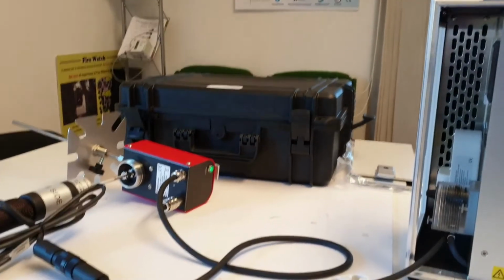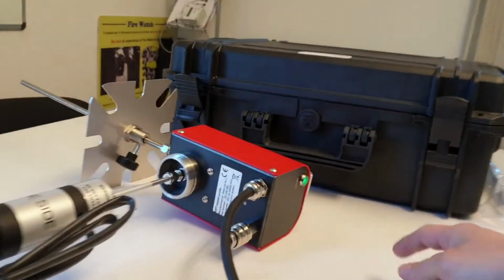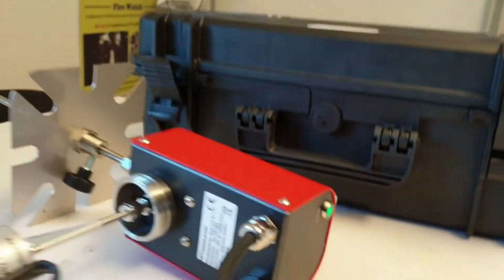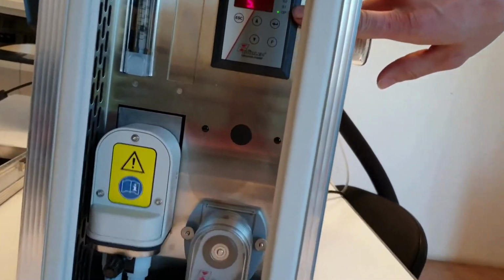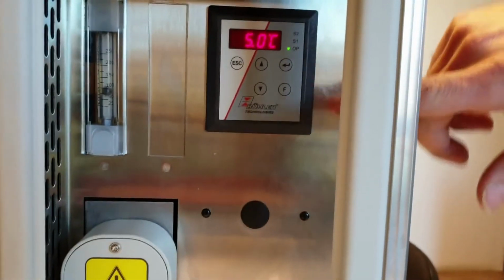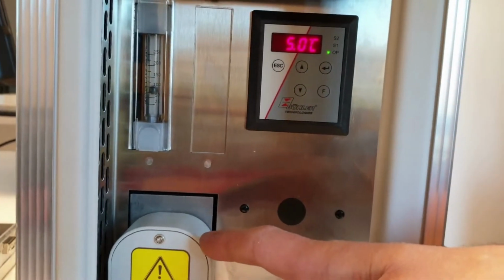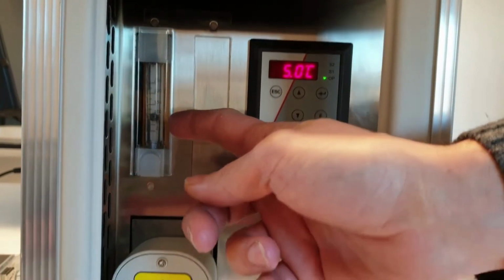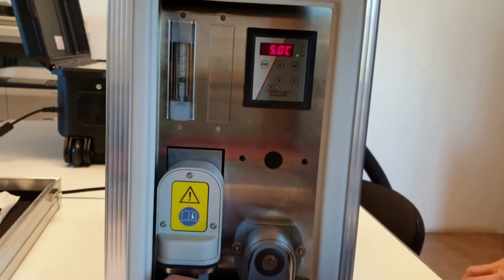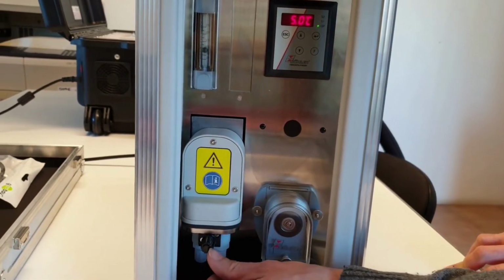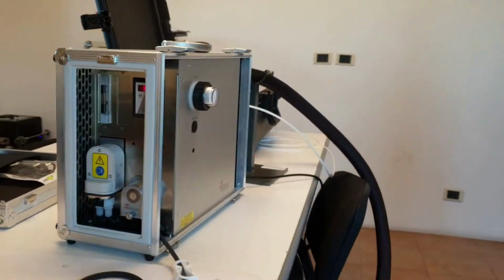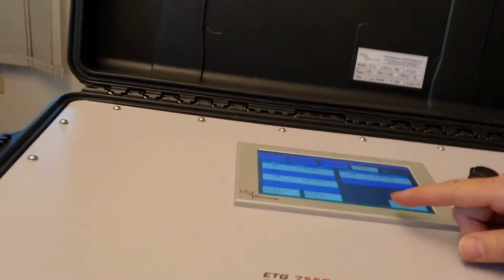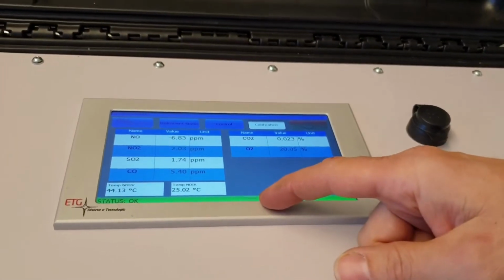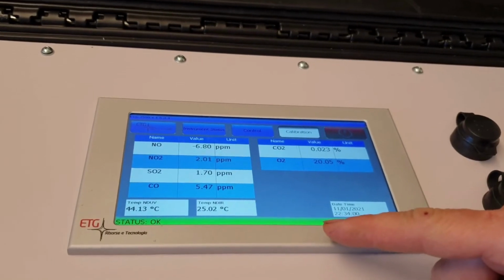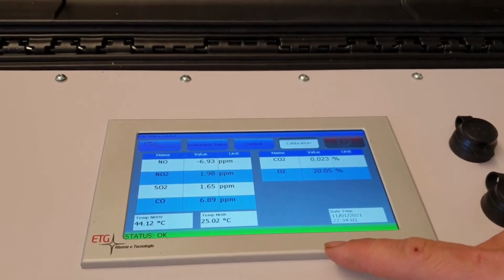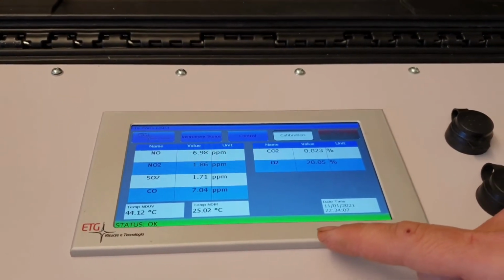Now the system is on temperature. You can see the green LED of the probe, the green LED of the sample conditioning unit, and also you can see that the pump is running because there is a flow. You can see it on the flow meter, and it's possible to regulate the flow through this valve. And also on the analyzer, the status bar is now green and the status is okay. That means that there is no alarm active.